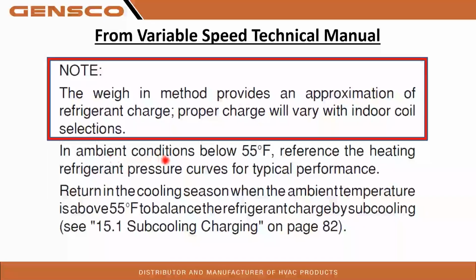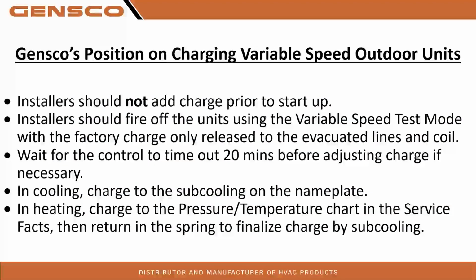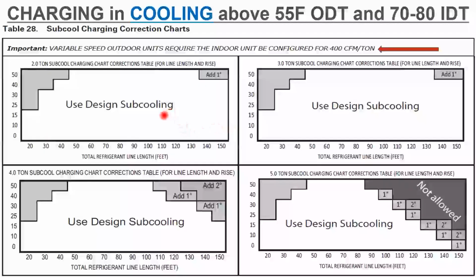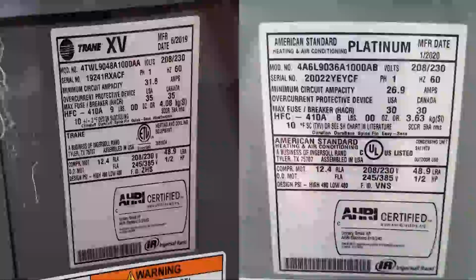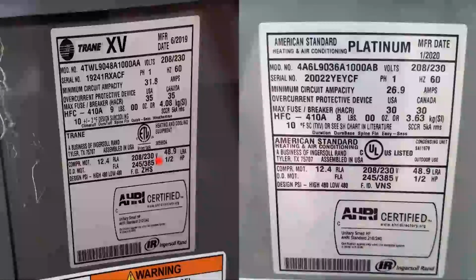So we're going to use our pressure curves in heating below 55 degrees, and above 55 degrees, we can use cooling to get a total subcooling charge. Charging and subcooling above 55 degrees outside temperature and a 70 to 80 degree indoor temperature. As you can see, this is our total linear feet. Use design subcooling. That design subcooling is going to be listed on your data plate.